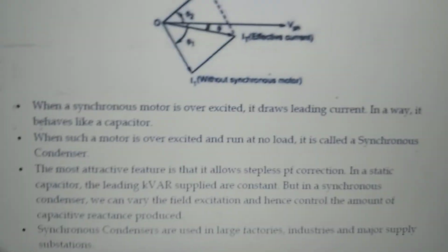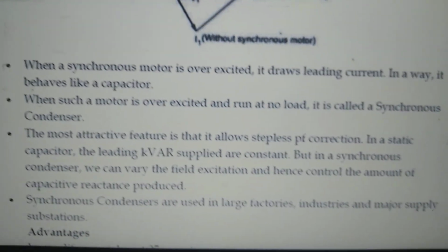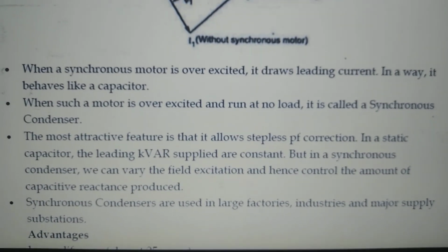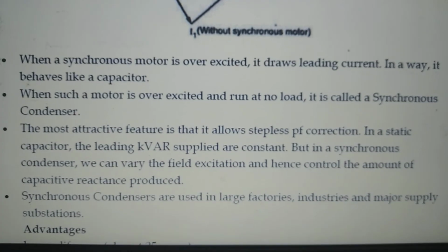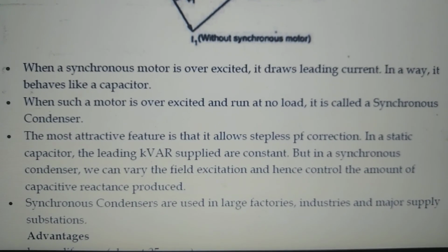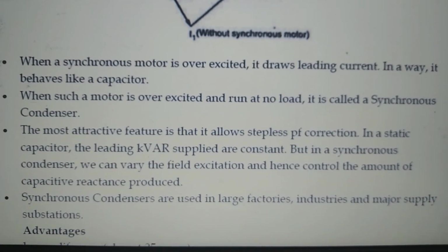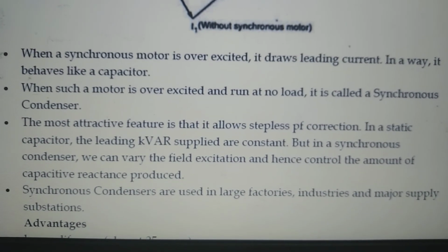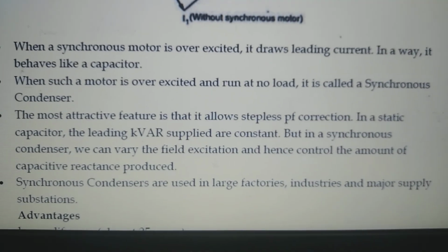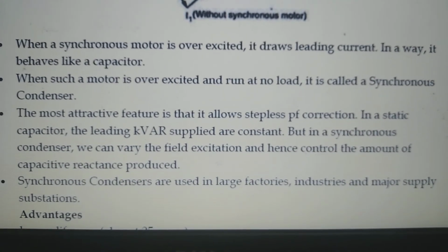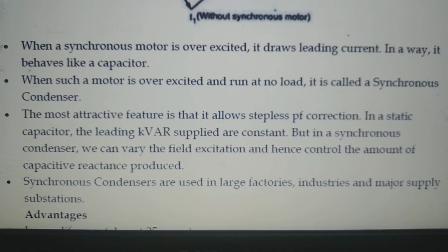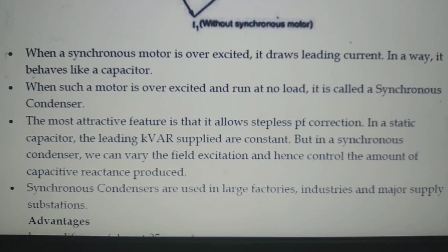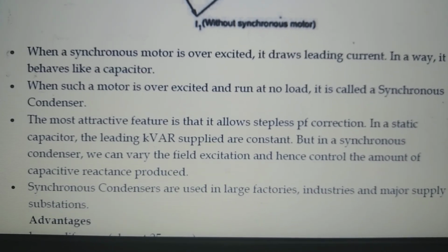Some points about the synchronous condenser: when a synchronous motor is overexcited, it draws leading current. In a way, it behaves like a capacitor. When such a motor is overexcited and run at no load, it is called a synchronous condenser. The most attractive feature is that it allows stepless power factor correction. In a static capacitor, the leading kVAR supplied are constant, but in a synchronous condenser, we can vary the excitation and hence control the amount of capacitive reactance produced.